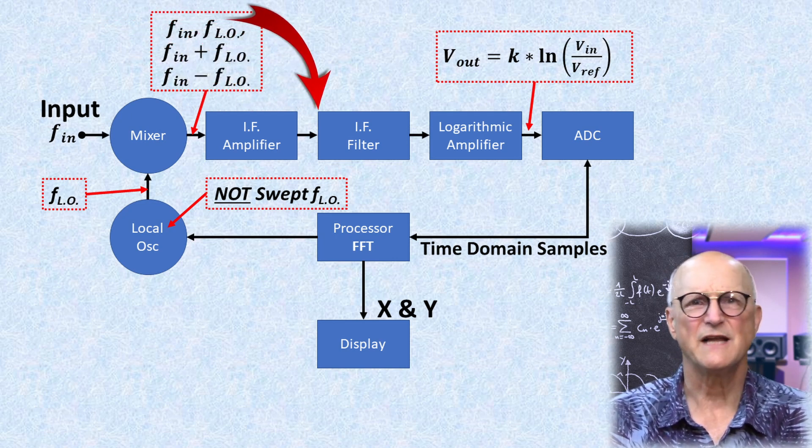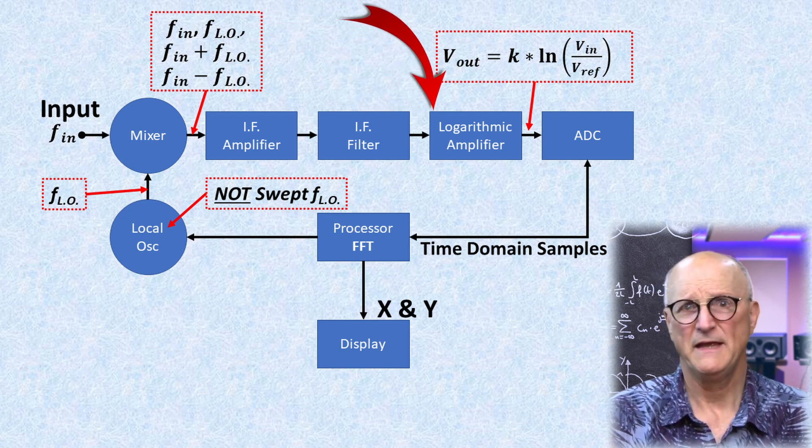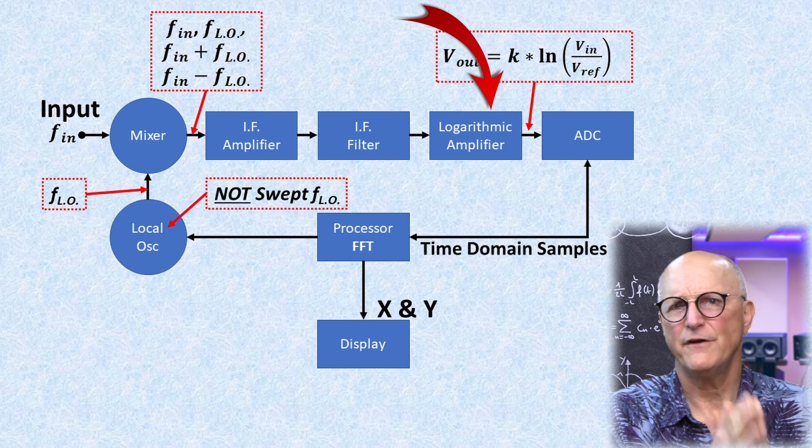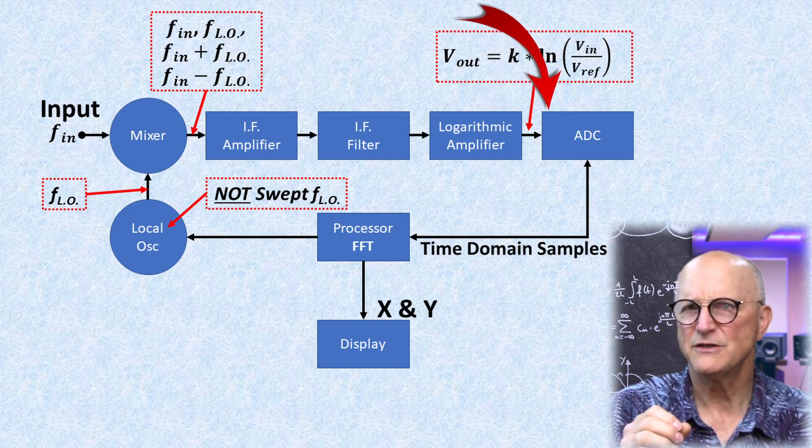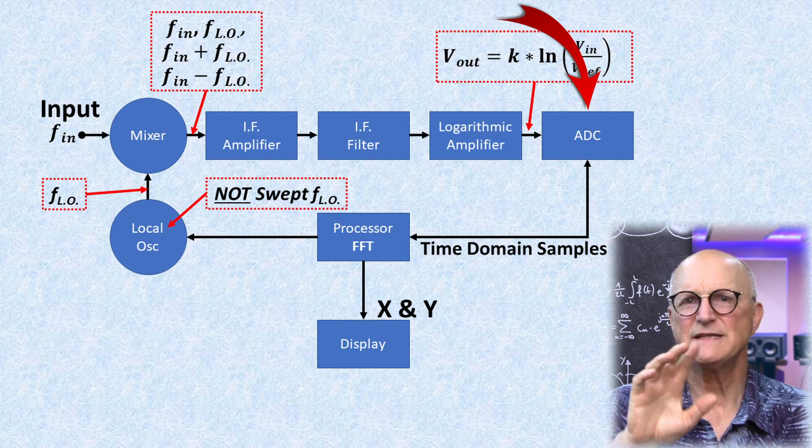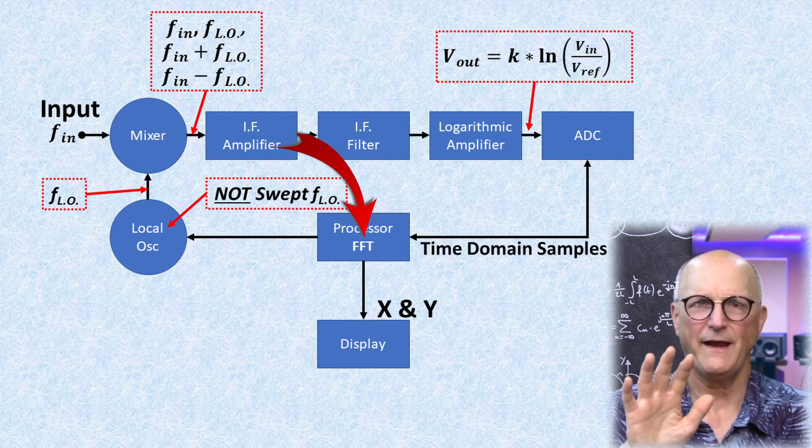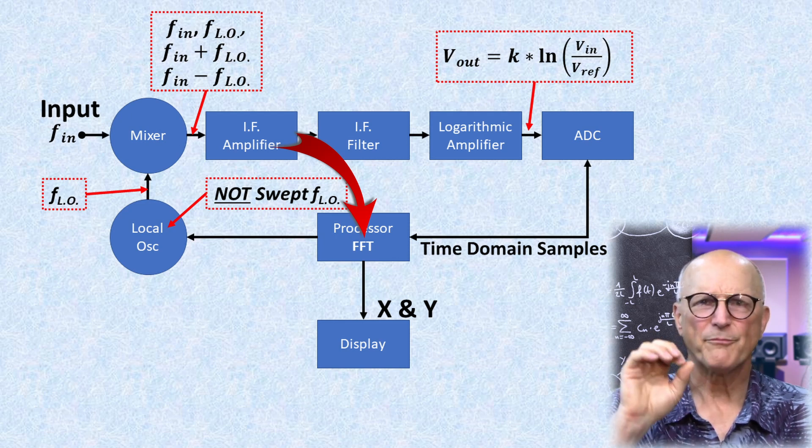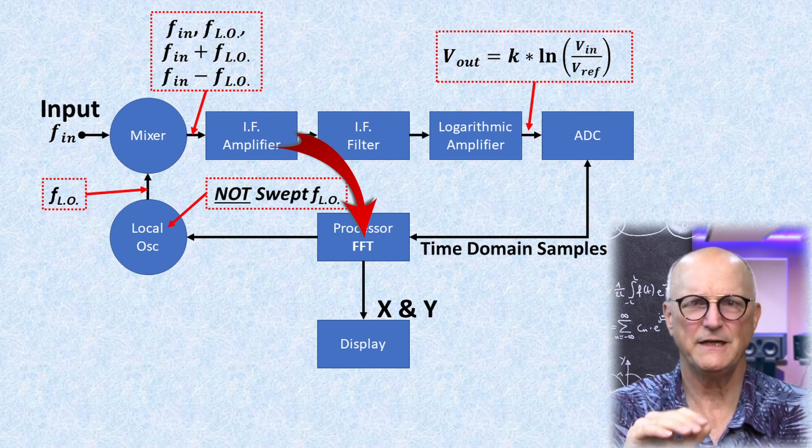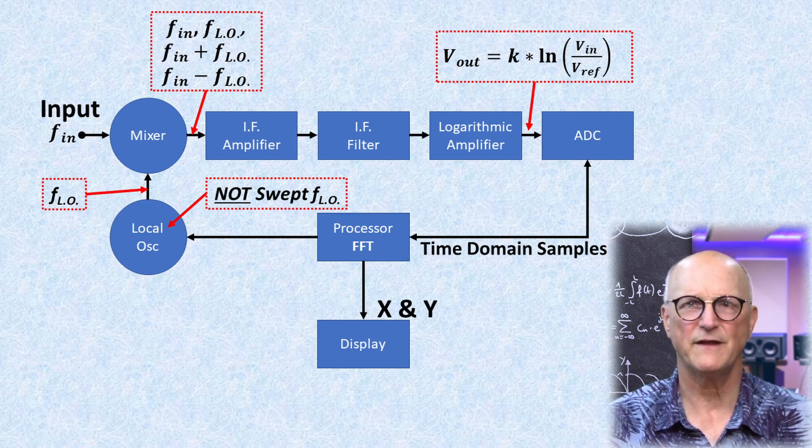The output of the heterodyne front end goes to an analog-to-digital converter, and with this hybrid approach, the IF is now sampled in the same fashion as they do for a Fourier analyzer. The processor does an FFT, and the display is then updated with the results of the FFT.